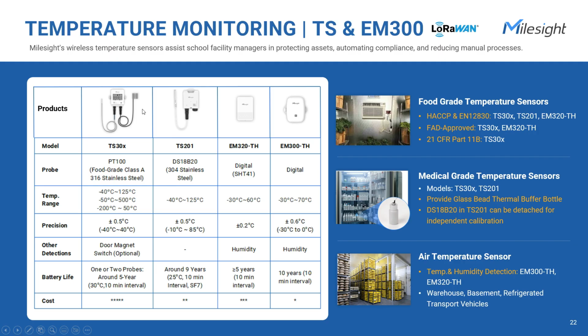Secondly, for medical-grade temperature monitoring, I highly recommend the TS30X and TS201 models. They can detect temperatures ranging from well below zero to over 100 degrees with extremely high accuracy, within about 0.5 degrees. You can also get an optional glass bead thermal buffer bottle, which helps stabilize readings when the air temperature fluctuates, like when doors are opened or coolers are loaded. This feature is especially useful for storing vaccines or liquid medications. In addition, the TS201 comes with a detachable sensing probe that can be calibrated independently. It's a much more affordable choice than the TS30X.